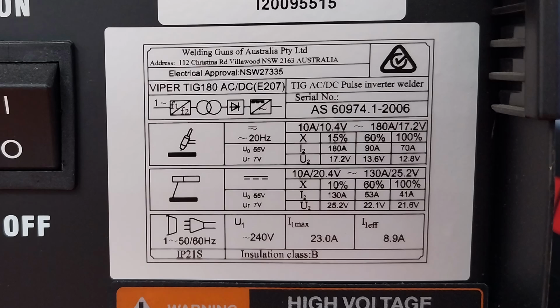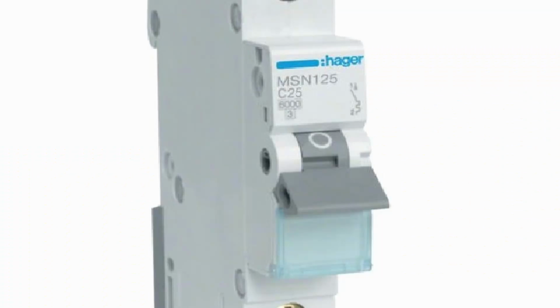There are a few high amperage welders on the market these days which come with 10 amp plugs - sounds good, doesn't it? As an example, here is a specification label for the Unimig Viper 180 amp AC/DC TIG machine. Here the maximum input current is 23 amps and the effective current is 8.9 amps. So to safely run, the welder circuit will need a 25 amp or better circuit breaker or fuse, and the welder a 10 amp plug, which it comes with. It's one of the highlights of the advertising for it.